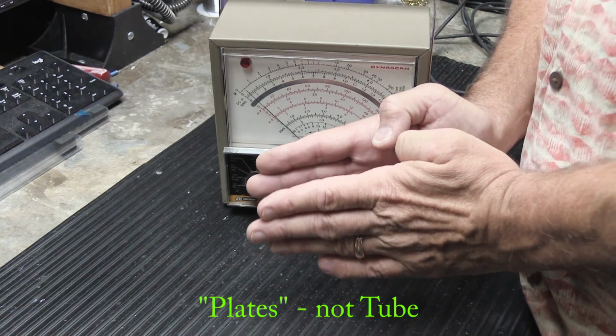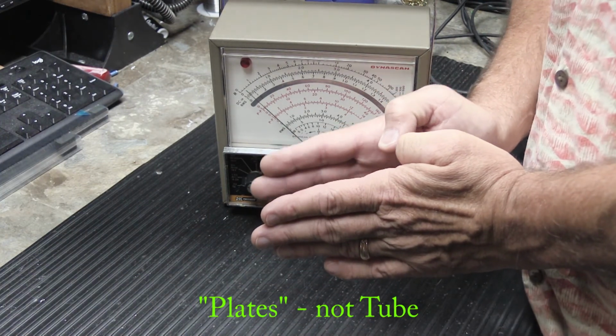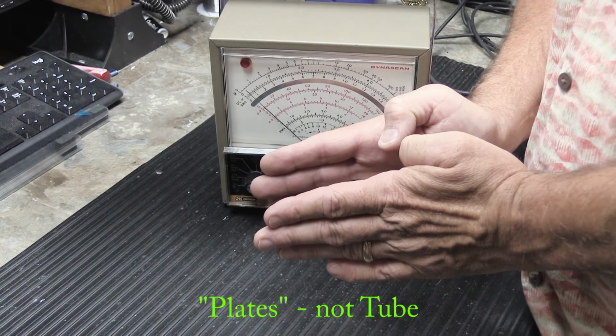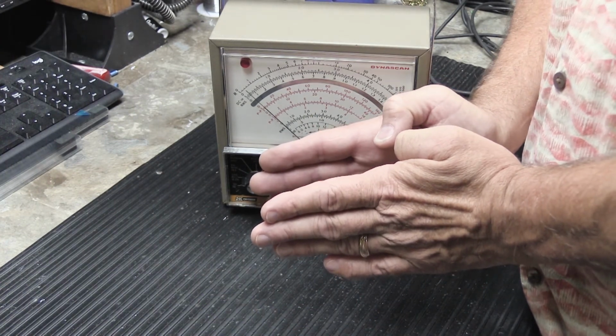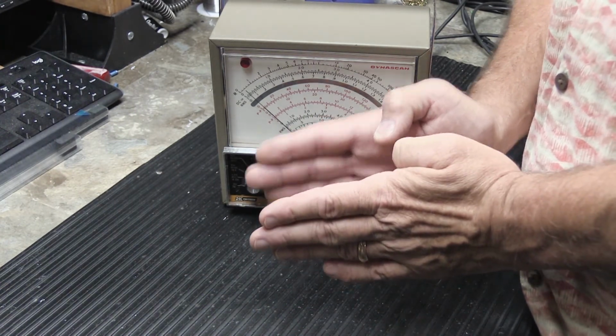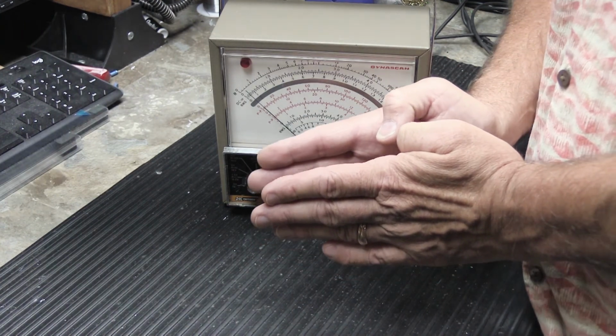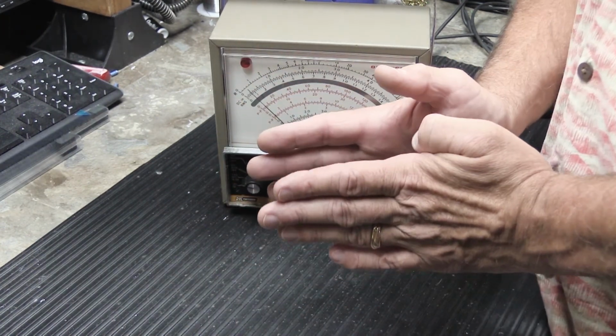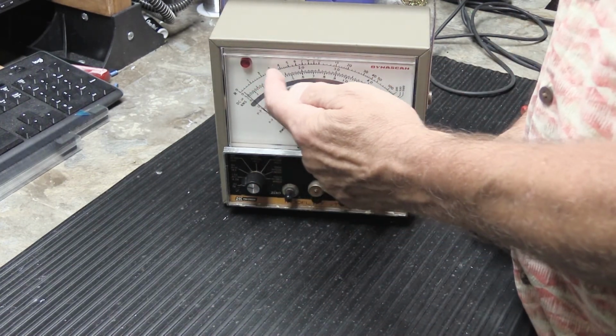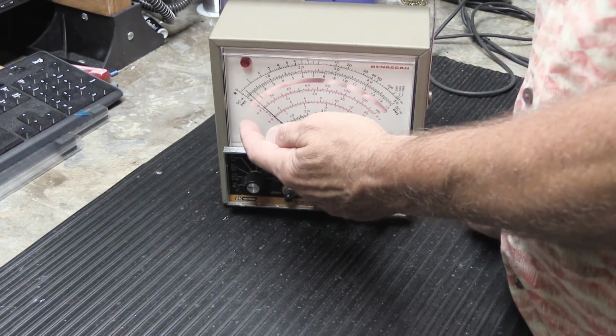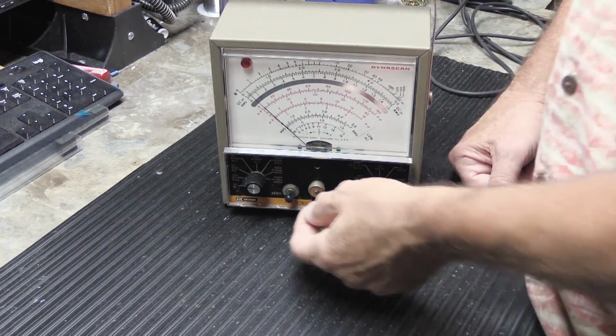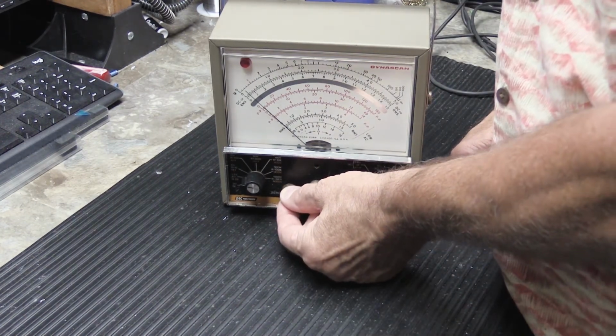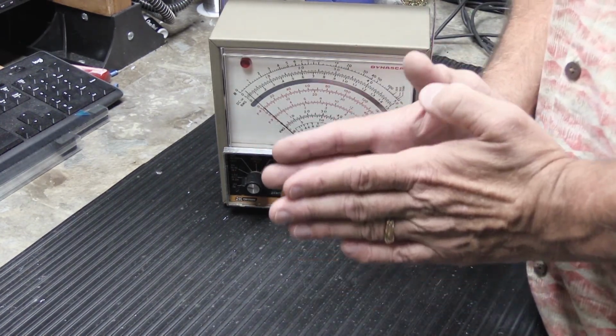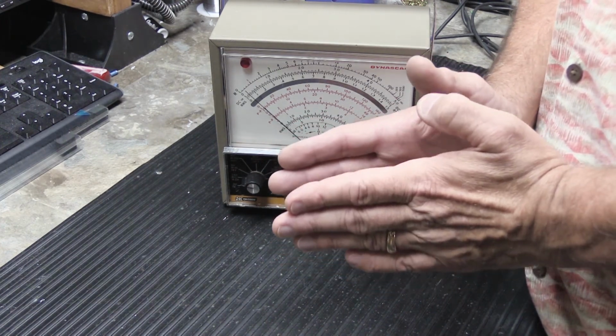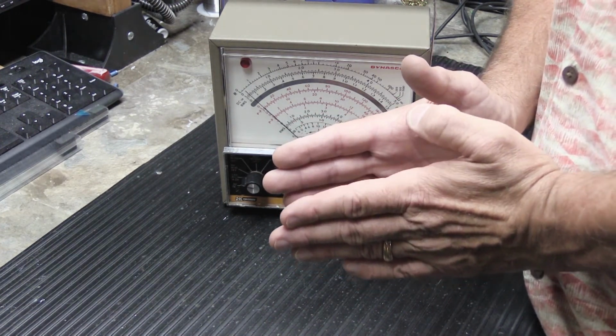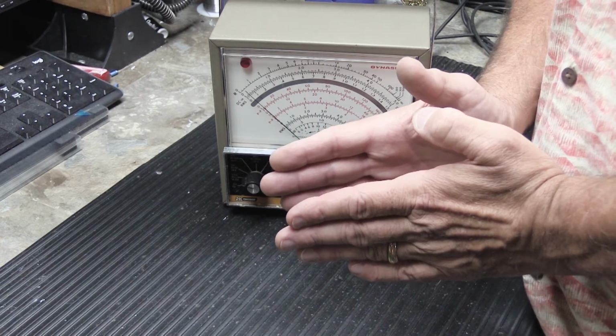If this vacuum tube has 2 volts on it and this vacuum tube has 2.5 volts on it, the needle is out of balance. You need a balance. You need 2 volts and 2 volts at the same time, so the needle will go to 0. If it's 2 and 2.5, the needle's either going to read high or the needle's going to read low, and you want it right on 0. So this adjustment here balances out the voltage between the two sections or the two plates to achieve 2 volts and 2 volts, so the needle rests on 0.